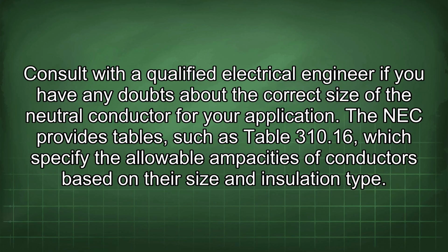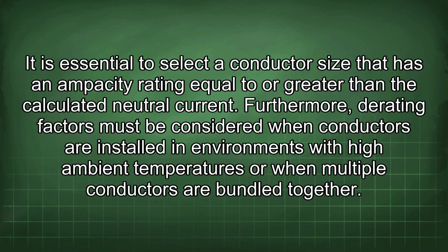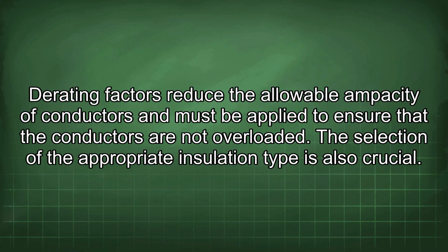Consult with a qualified electrical engineer if you have any doubts about the correct size of the neutral conductor for your application. The NEC provides tables, such as Table 310.16, which specify the allowable ampacities of conductors based on their size and insulation type. It is essential to select a conductor size that has an ampacity rating equal to or greater than the calculated neutral current. Furthermore, derating factors must be considered when conductors are installed in environments with high ambient temperatures or when multiple conductors are bundled together. Derating factors reduce the allowable ampacity of conductors and must be applied to ensure that the conductors are not overloaded.